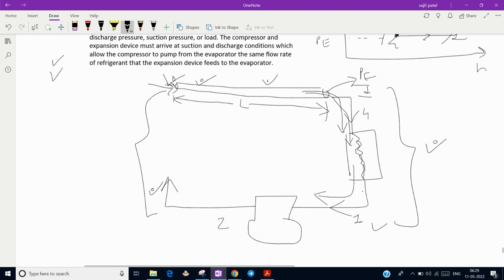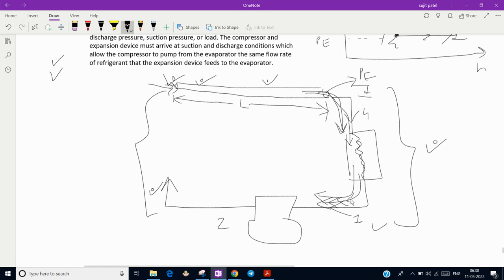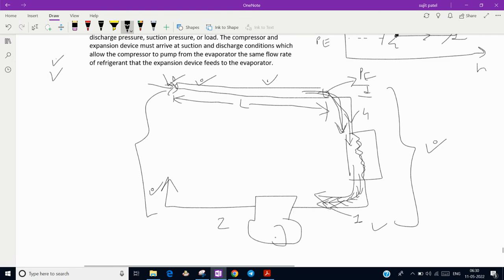In the other case, capillary tube is giving less mass flow rate but compressor is trying to extract more, so there may be chances to create vacuum and the pipes of evaporator may get compressed if excess pressure is given. Air or other gases will get trapped in the compressor and ultimately decrease the volumetric efficiency and overall efficiency of the cycle.